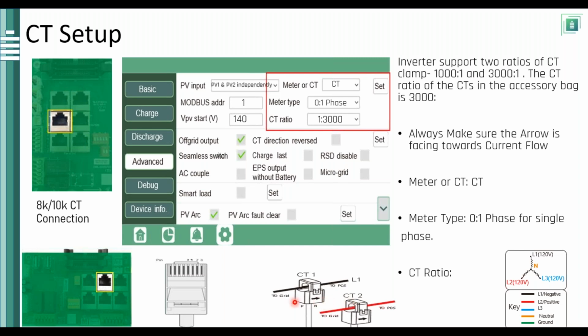Make sure that when you're installing the CTs, the arrow is pointing in the direction that's going into the inverter, right? So if I am looking at this arrow right here, this side would be grid and this side would be the PCS or power conversion system, which would be your inverter, right? Make sure that when it says CT1, it goes on line 1, CT2, line 2.